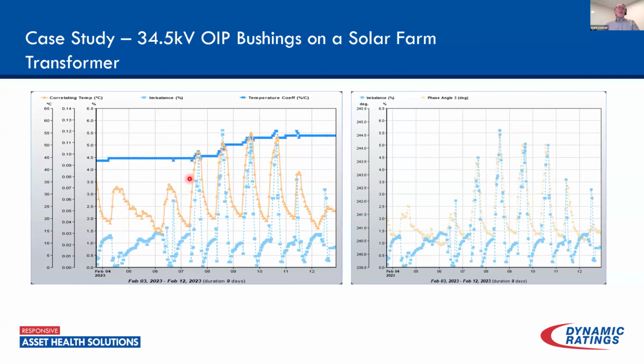What I'm seeing is that as the imbalance current changes, it's correlating with temperature. So when the temperature is low, my imbalance is low, but when my temperature is elevated, I see a higher imbalance. The reason is that power factor is heavily temperature dependent, and the more moisture you have in your insulation, the greater the problem is going to be in there. And the monitor is detecting and identifying this.